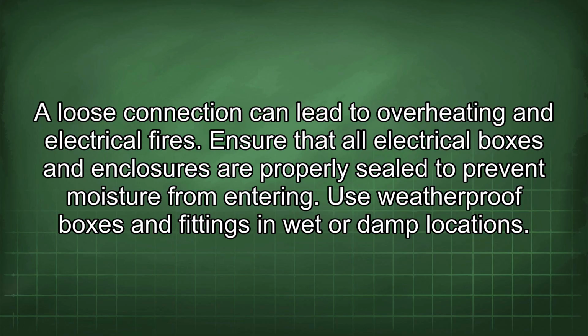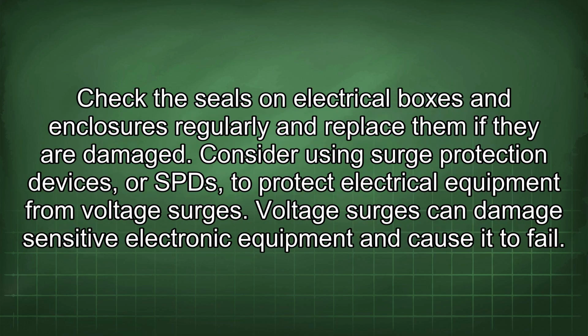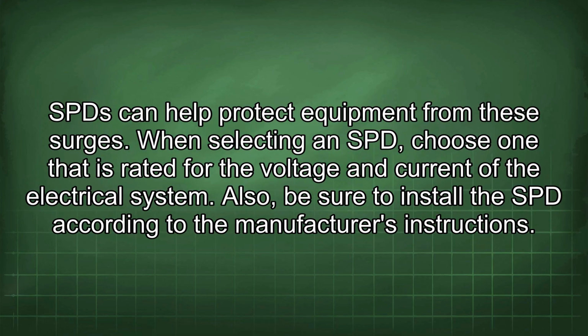Ensure that all electrical boxes and enclosures are properly sealed to prevent moisture from entering. Use weatherproof boxes and fittings in wet or damp locations. Check the seals on electrical boxes and enclosures regularly and replace them if they are damaged. Consider using surge protection devices, or SPDs, to protect electrical equipment from voltage surges. Voltage surges can damage sensitive electronic equipment and cause it to fail. SPDs can help protect equipment from these surges.